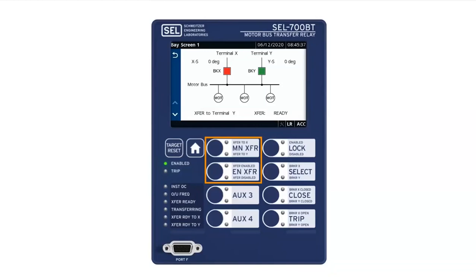Okay, thank you. What's the advantage of using the 700BT for a main-tie-main setup versus the 751 three-box solution using our app guide? In this one, the 700BT does the in-phase transfer, which is not possible with 3-cycle frequency measurement. Also, you saw we have very few settings. The application guide is also well tested, but when you have to write the logic, I think everyone will agree that the hard-coded logic is better. Also, we track a way higher rate of change of frequency. The 700BT will do bus transfer up to 35 hertz per second, which we cannot measure in any other relay. Thank you.